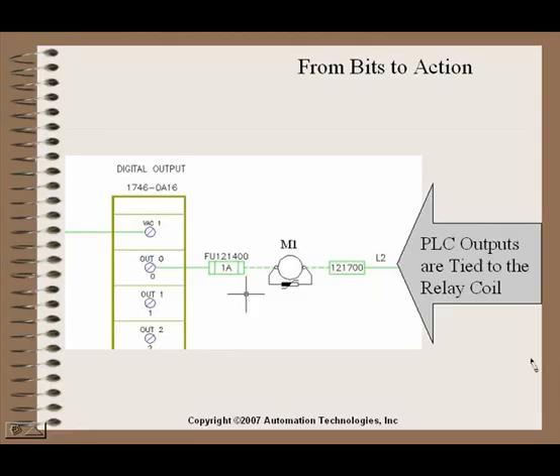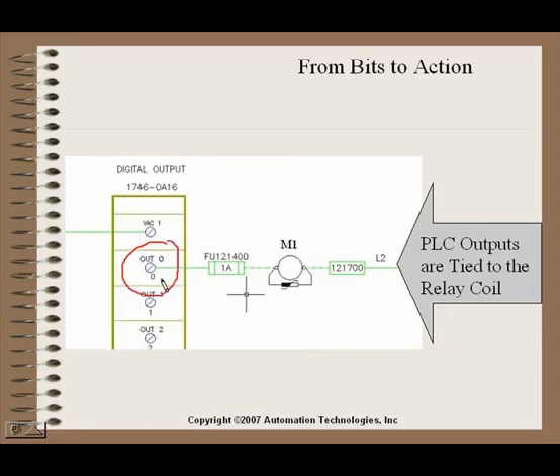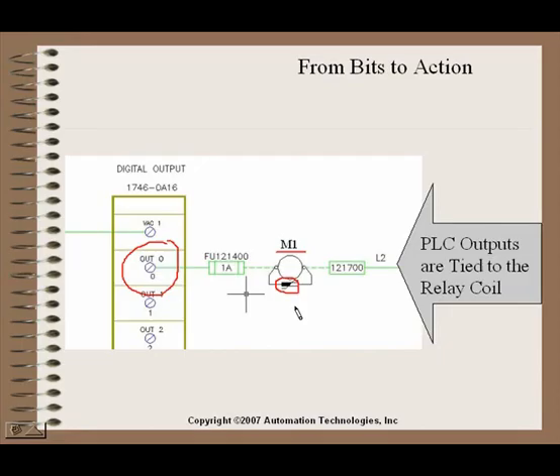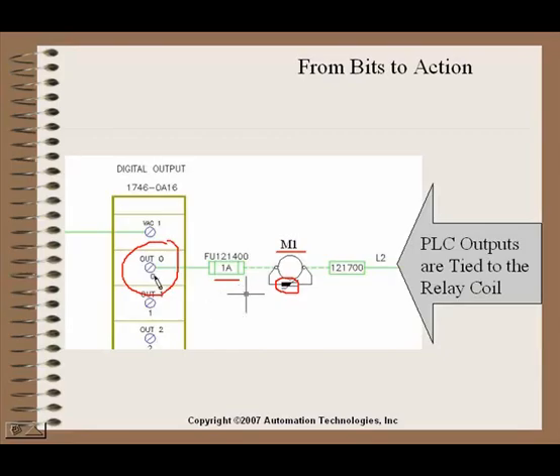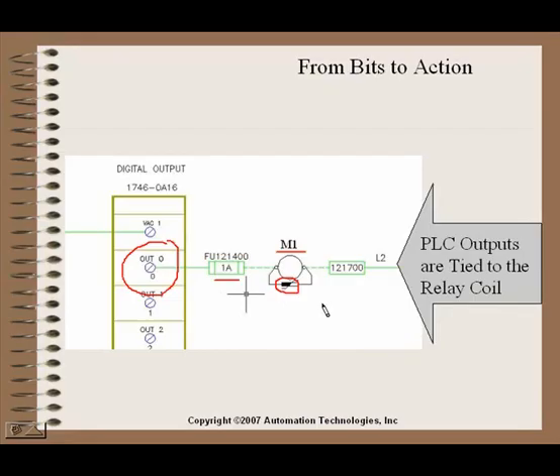Likewise on the other side, we have our outputs, our PLC outputs, which is a different type of card that interfaces directly to our relay, motor contactor M1. You see it has a surge suppression device around it to protect the PLC output. Also a fuse to protect the output, but generally the main thing you have here is this output directly from the PLC that goes to a relay coil to be able to operate some kind of real world device.